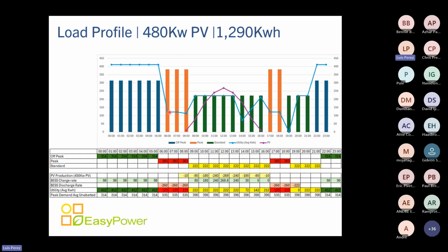It sees a noticeable decrease because we are physically offloading our energy. We are doing arbitrage, trading our energy back with the tenants. Then it sees the energy demand go up again, since we are now busy recharging our battery from solar. And then after the battery is full, you will see physically how our energy goes down again. And as the solar tapers down, the energy starts going up again. Then we enter the next peak for operation, which is your evening peak. So again, we go down.